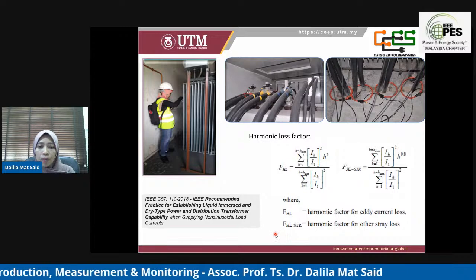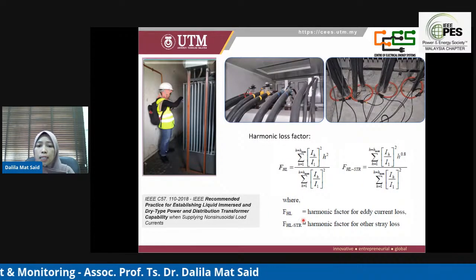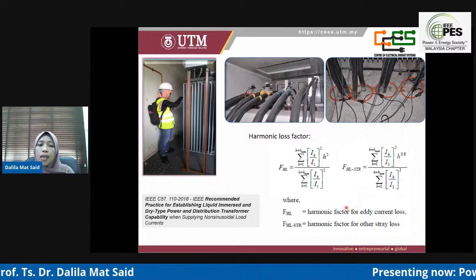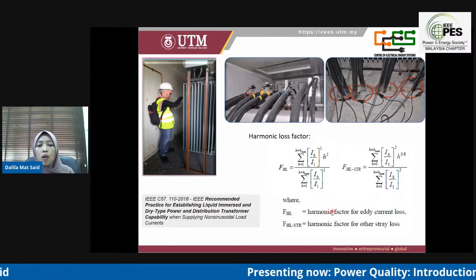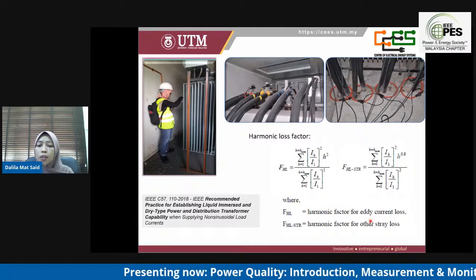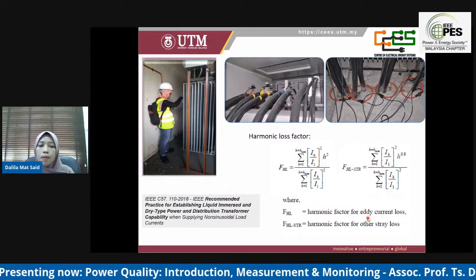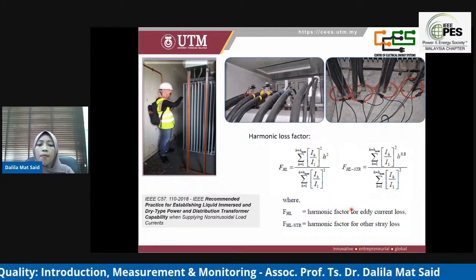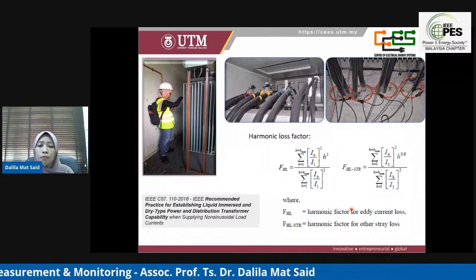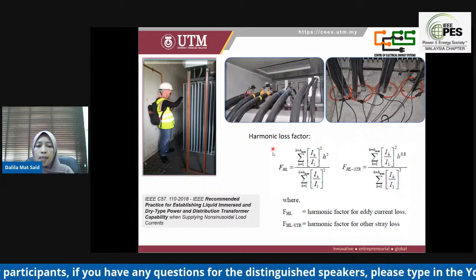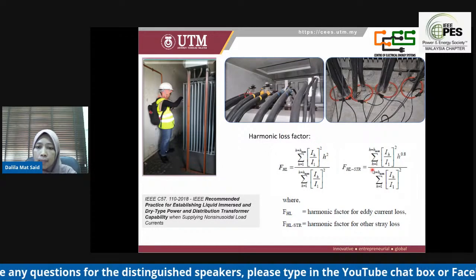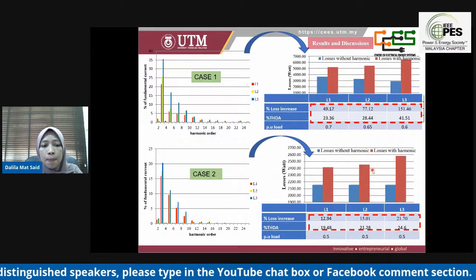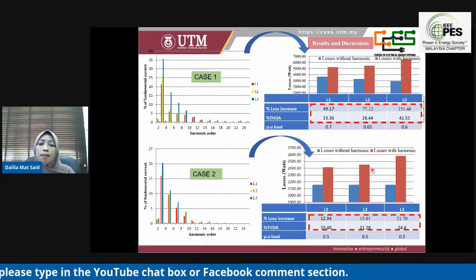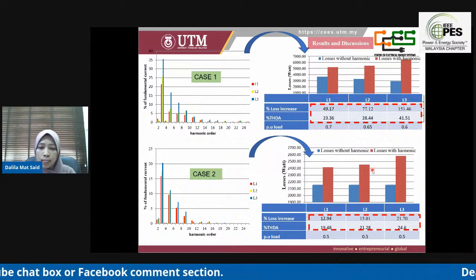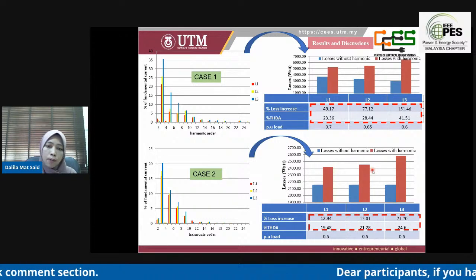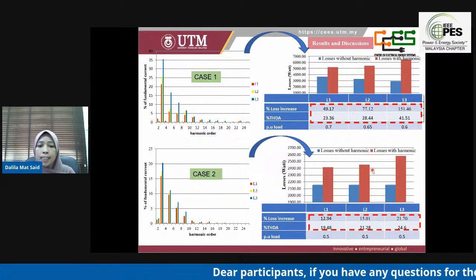IEEE C57.110 developed the harmonic loss factor as a method to determine the summation of harmonic orders. This factor can be used as a multiplier on the winding eddy current losses and also other stray losses. Both factors can be normalized to either the fundamental current or the RMS current, and we can see the formulation for the factor here. By using this formulation and considering all the harmonic losses in the transformer for the load losses, two different case analyses have been considered.